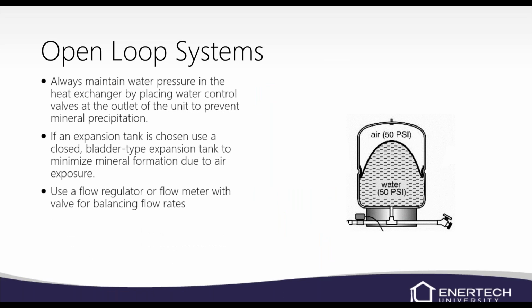On an open loop system, always maintain water pressure in the heat exchanger by placing the controls, so those solenoid valves, on the outlet of the unit to prevent mineral precipitation. Basically what will happen is if we were to put the valves on the inlet, when the valve goes to shut off, all the water would drain out of the heat exchanger, and there would be some residual water left hanging in there. And as it dries out, the minerals stick to the walls and cause poor heat transfer. So you have to clean the system more often. So make sure you're putting them on the outlet, so when the valve shuts off, the heat exchanger stays full of water. It stays flooded.